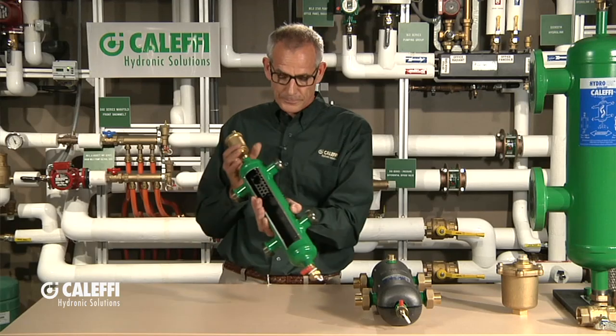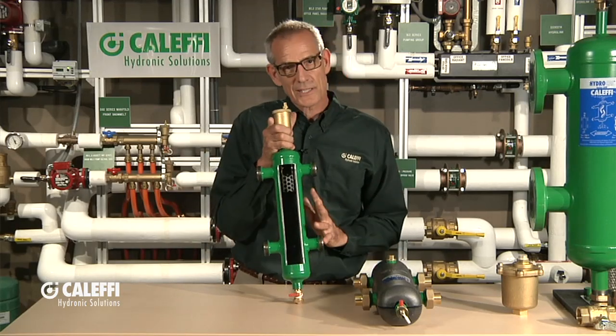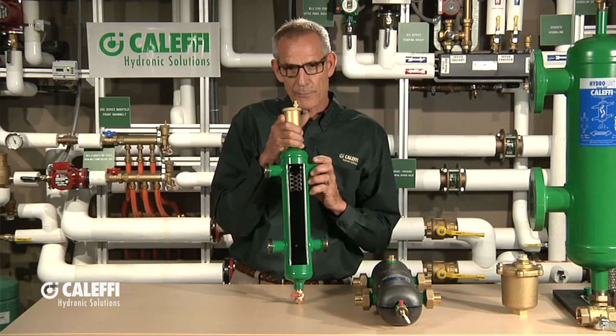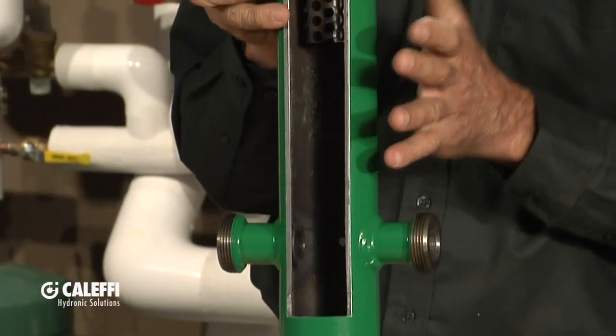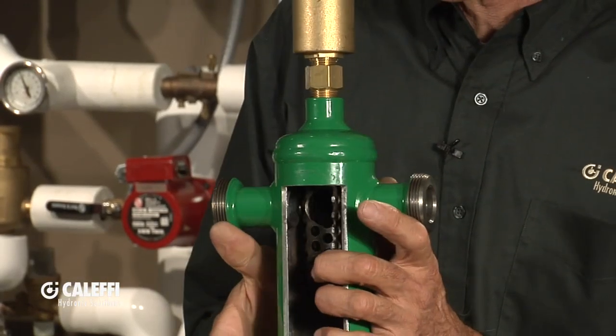Probably the best way to do that is I brought a cutaway along with me here. So this is the Caleffi hydro separator. Basically, what a hydro separator does is it separates the primary from the secondary side. Think of it as closely spaced T's here and closely spaced T's here.